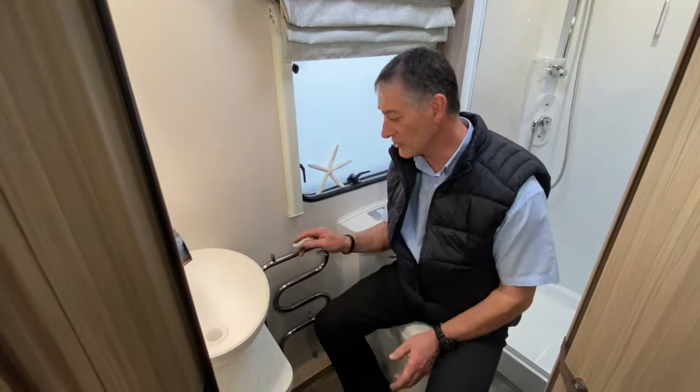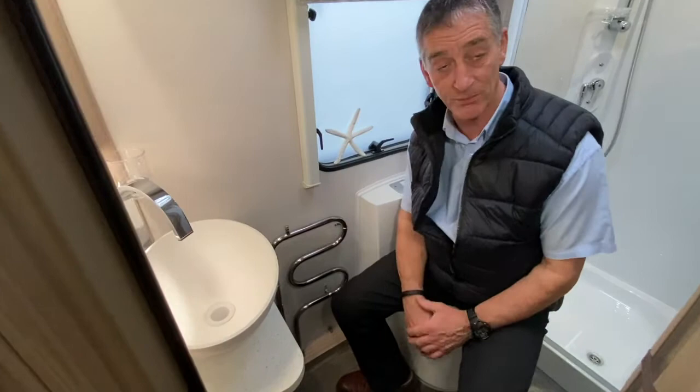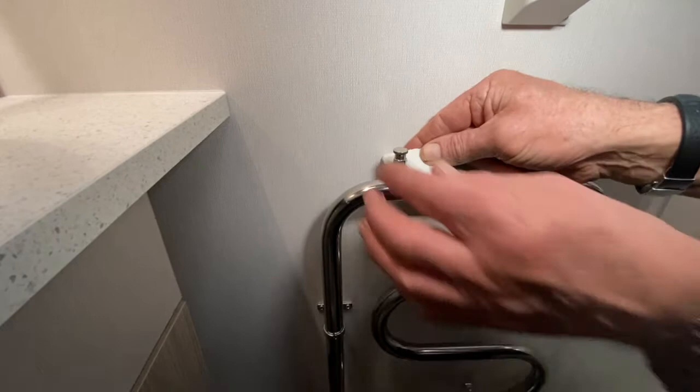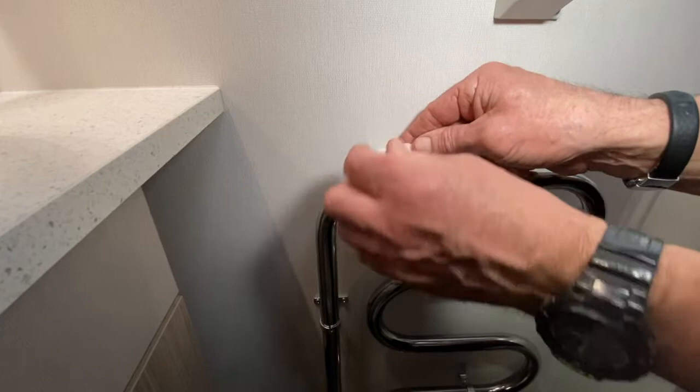I'm going to show you a couple of things on the Alde heating system. The first part is where we can bleed air out of the radiator system itself. This is the bleed valve and we've got a little nipple that protrudes beyond the radiator just there. Get a tissue of some sort, open up the bleed valve. You're going to see water come out — there it is. Just catch any of the fluid that runs out, and that's it. We have got the air out of that particular radiator.